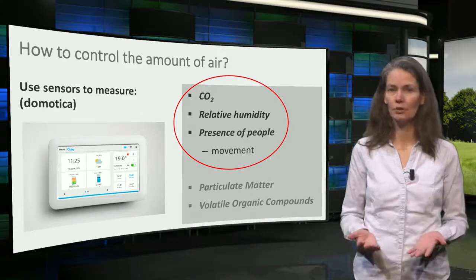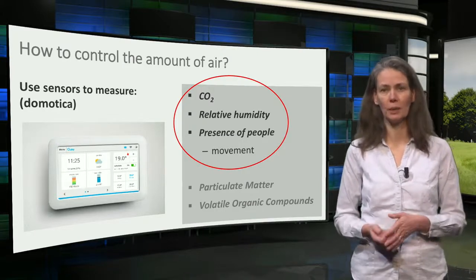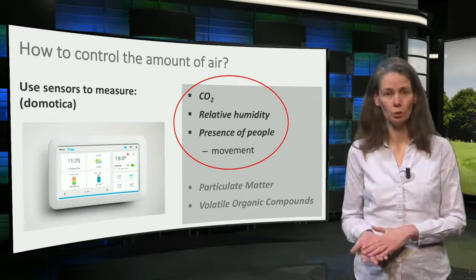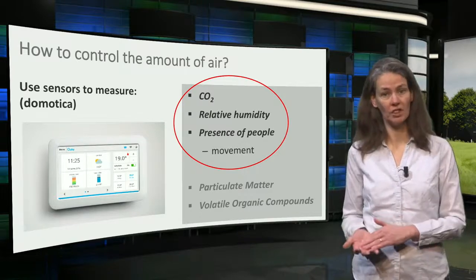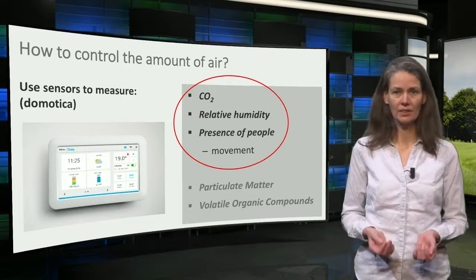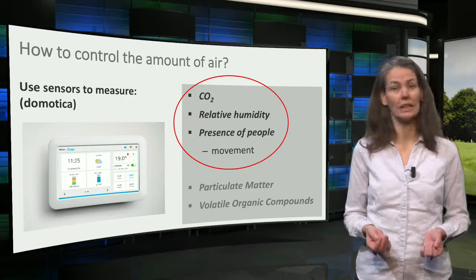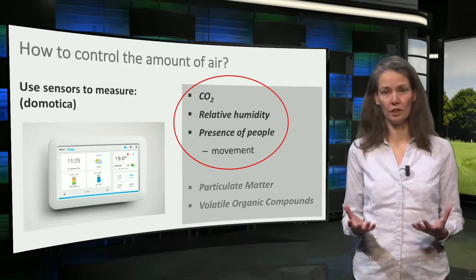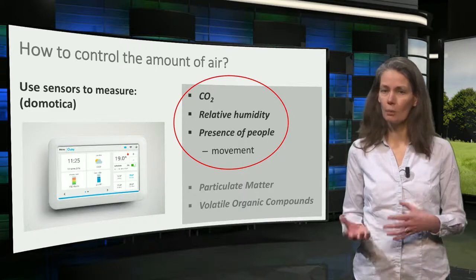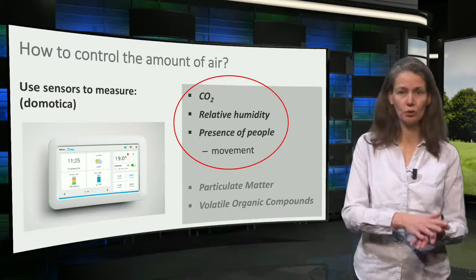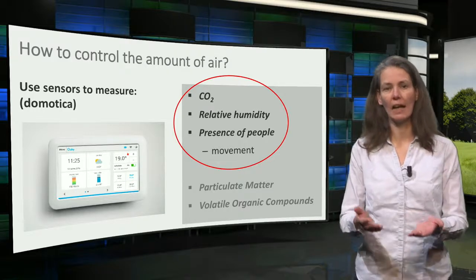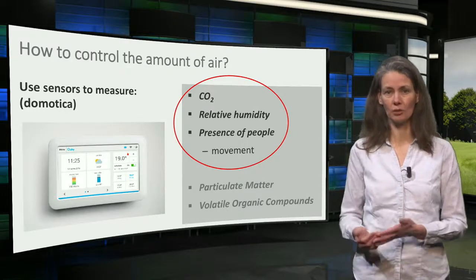At this moment, it is possible to measure the amount of people with movement sensors, for example, the CO2 related to indoor air quality, and the relative humidity. Measuring other gases and particulate matters is also possible, but more difficult and expensive. Coupling these sensors to the ventilation control systems ensures the right amount of ventilation at the lowest energy demand.